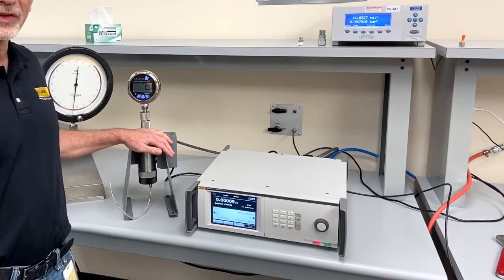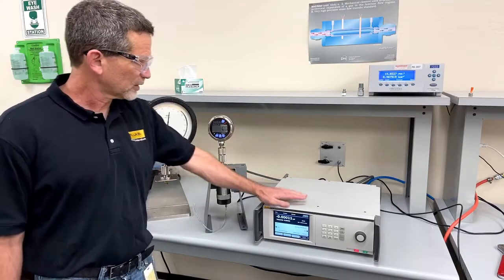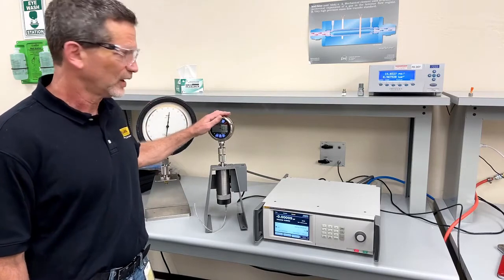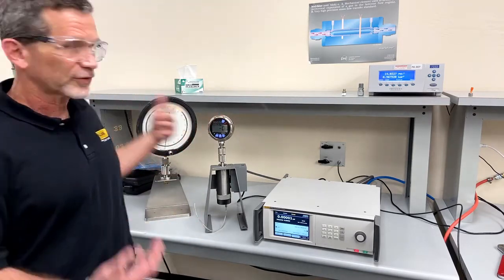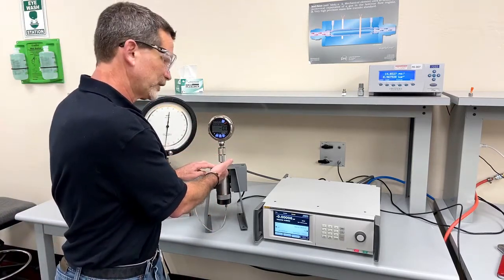What we have here is the accessory called the contamination prevention system. It protects the pressure controller from the contamination that may be in the device under test that comes from its industrial use, whether it's liquid or particulates.